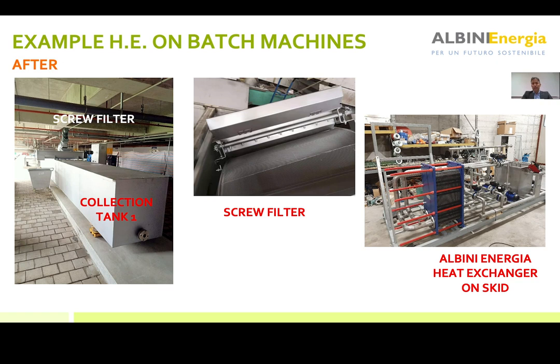In this case, it was pretty important to us to guarantee a compact solution, and that's the reason why we chose the plate heat exchanger - an economic solution. You will see later on that the number of working hours and the flow of the system was not big enough to have a good payback with pipe shell heat exchangers, so we prefer to have the screw filters on both sides in order to protect the plate heat exchanger that we actually used.